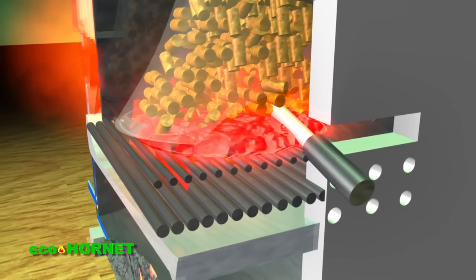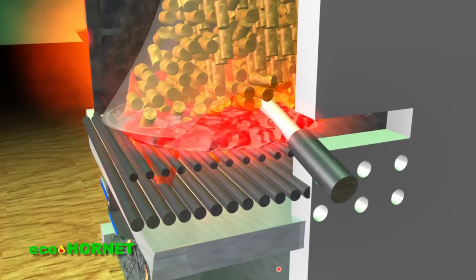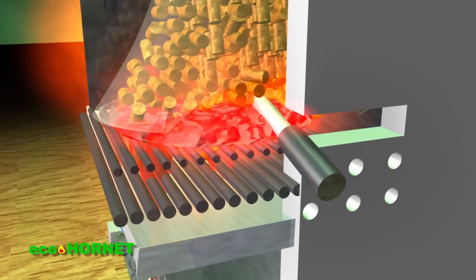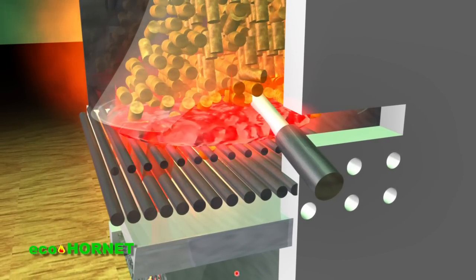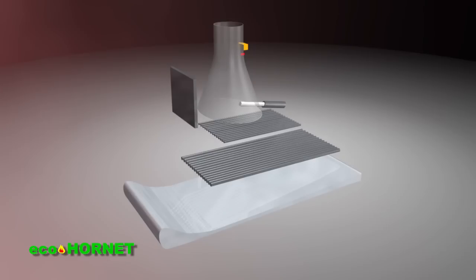The on-off operation of the heating system, as controlled by the room temperature set using the ambient thermostat, is the most efficient operation mode. The burner is formed of 3 grates, 2 of which ensure constant circulation for the combustion of 6 mm pellets, and the third holds the incandescent pellets until their diameter is reduced below 3 mm.